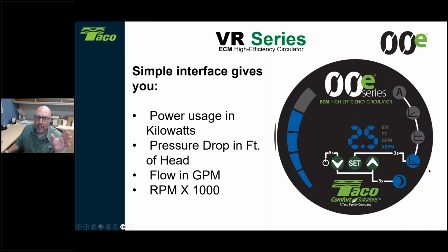The one that is highlighted on the screen right now is showing me a fixed speed mode, which means the circulator never changes speed. It would be, say, a zone pump style system or a length of pipe going there and back with no other valves in its way, meaning control valves or zone valves. The next one up, right here in the middle at the 3 o'clock position, is my constant discharge pressure, which now means it's a variable speed circulator when it's running. It will depend upon the system. When valves are opening and closing, it will speed up and slow down.